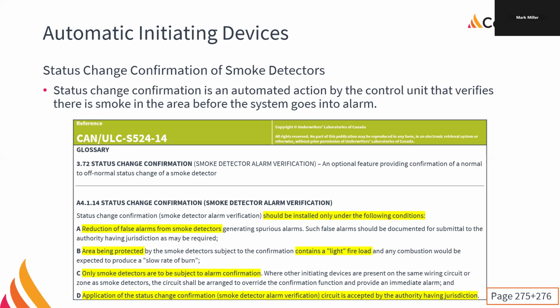Is it concrete and drywall and things like that, or is it wood paneling, wall to wall shag carpet? So if the area is extra burny, with lots of things that are quite flammable, they're probably going to say no, because the status change confirmation delays the inevitable. The other thing is only smoke detectors can be subject to the alarm confirmation, the status change confirmation. So if we have heats and pulls on the zone, we have to remove them from that zone. Right, so we have to rearrange it.